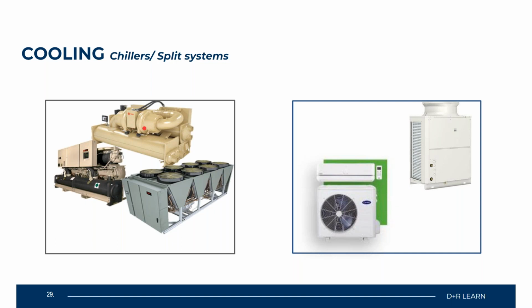So when you have applications such as campuses that require cooling, you're probably going to enlist the help of a water-cooled chiller, and you will have this located within a mechanical plant. The biggest difference between your water-cooled chiller and your air-cooled chiller is that the water-cooled chiller is going to come with a component known as a water tower or a cooling tower. But other than that, both these systems are going to be supplying chilled water at roughly 44, 43 degrees Fahrenheit on average, if we're talking about a facility or a campus. You're going to be producing 44 to 43 degree chilled water to your air handler coils or your fan coil units if you have those installed throughout your different facilities.